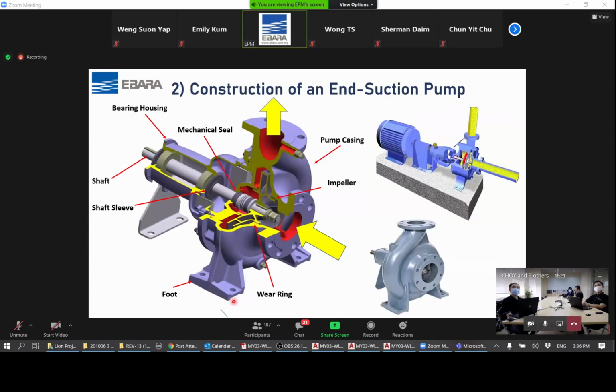Now, from vertical multi-stage pump, we move on to the next pump, which is the very common pump, what we call the end suction pump. Now, this pump is one of the oldest pump designs in the market. The design itself is more than 100 years old, but it has stood the test of time for many reasons, both from cost point of view, durability, as well as the ability to have a large flow range within a pump model. Now, this pump is typically what we call a cast construction.